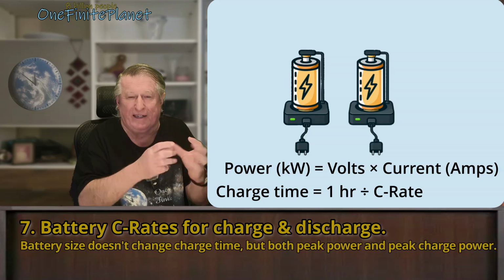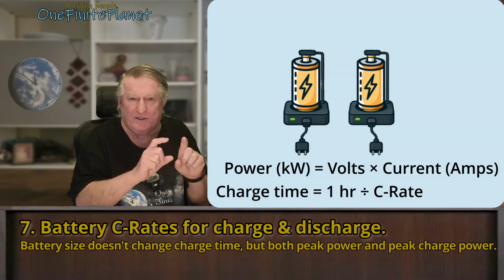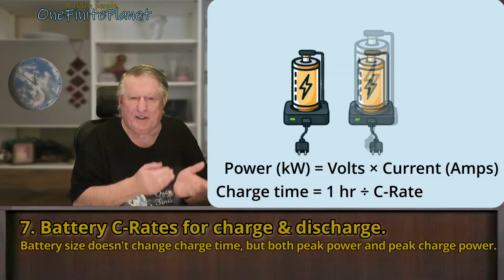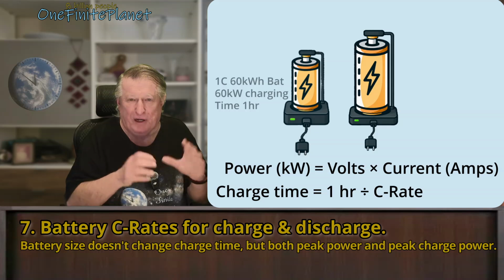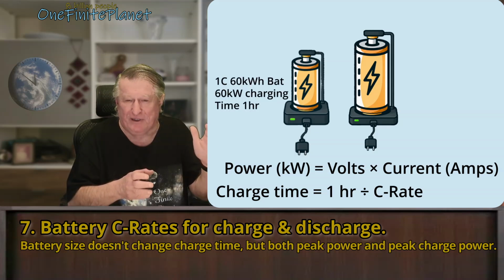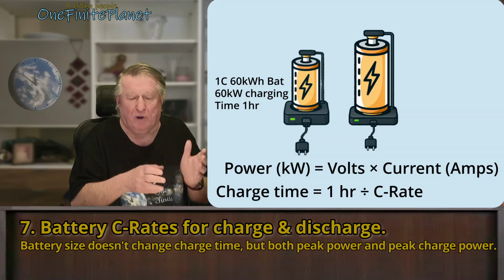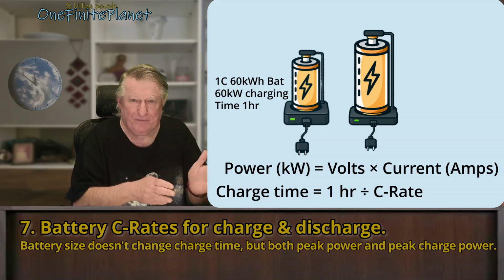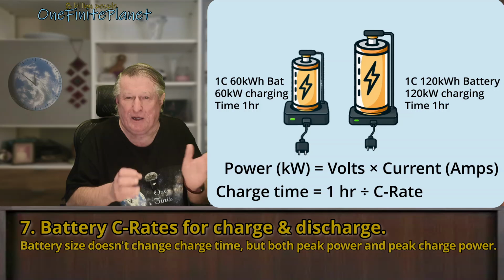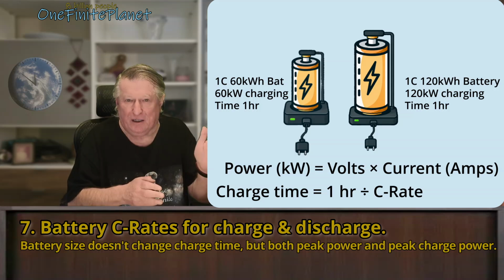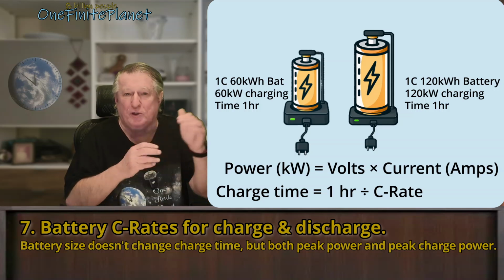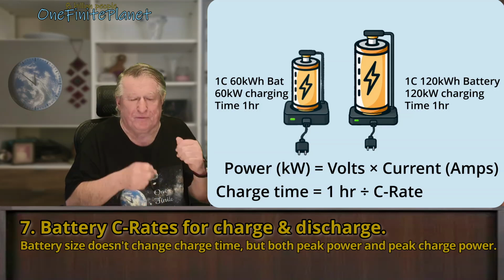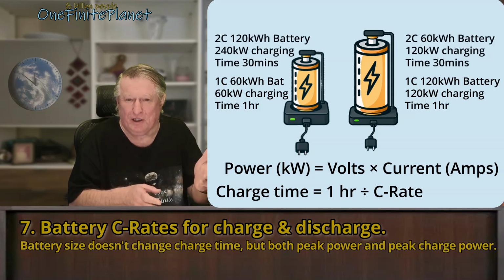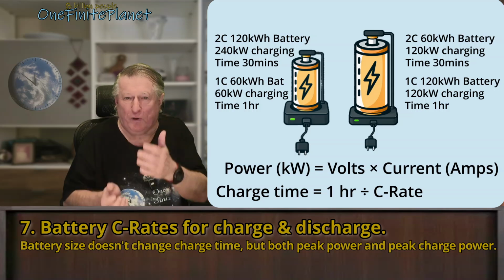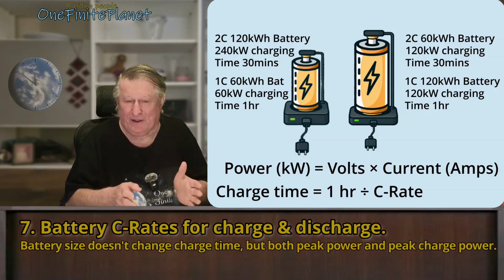They're both the same C rate no matter how much battery you've got. But the power to charge two batteries in the same time is double the power to charge one battery. So a 1C 60 kilowatt hour battery to charge in 1 hour will require a charge rate of 60 kilowatts. A 120 kilowatt hour battery to charge in 1 hour will require a charge rate of 120 kilowatts. 2C batteries of the same size would require 120 or 240 kilowatts to charge in half an hour.